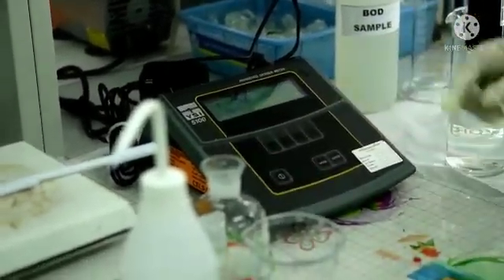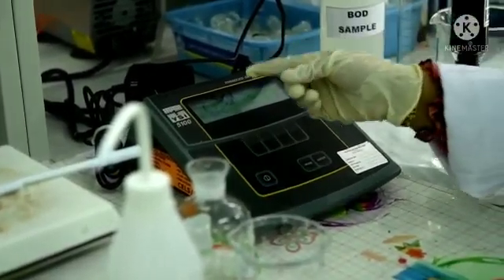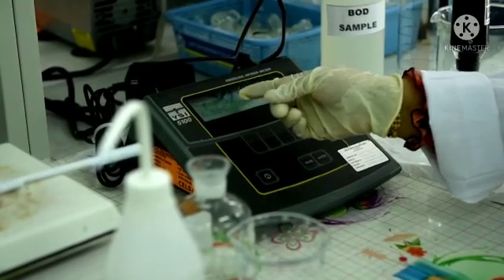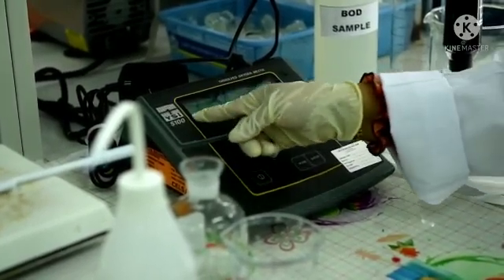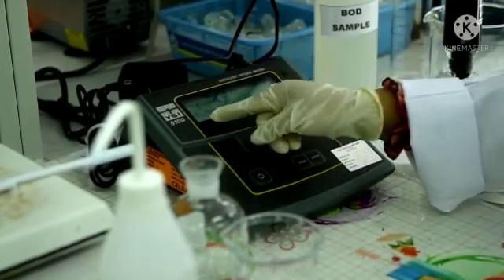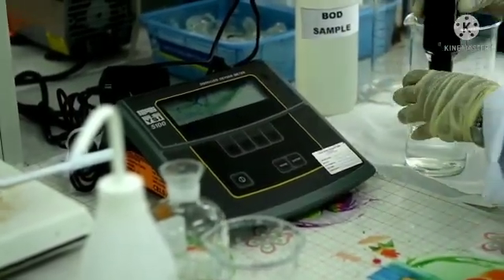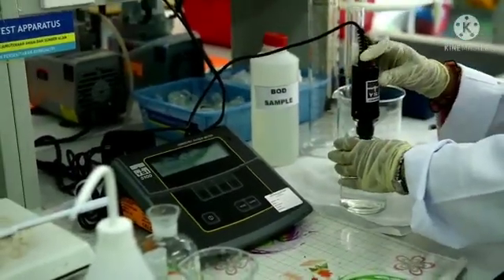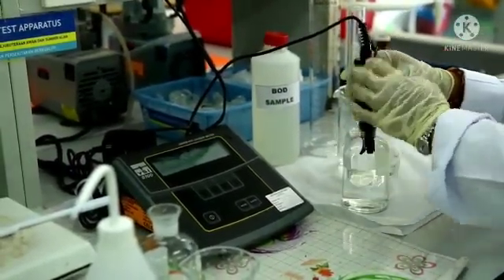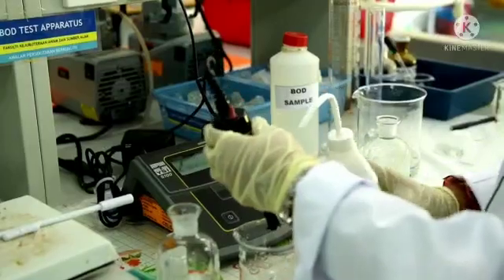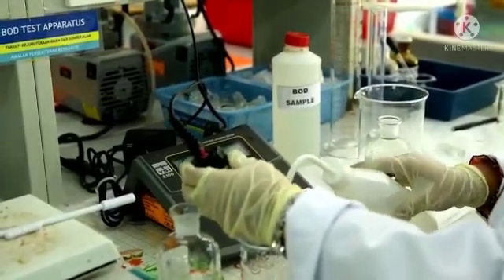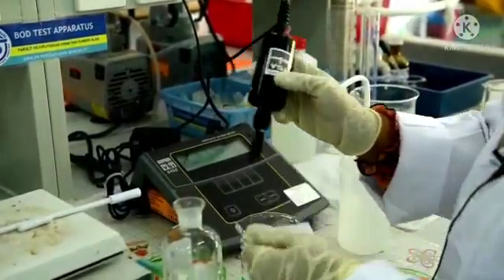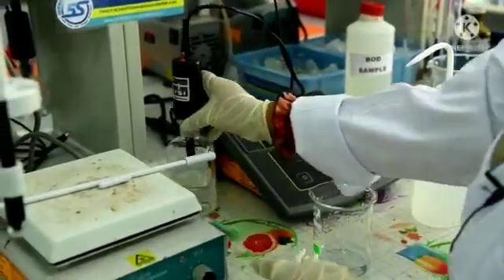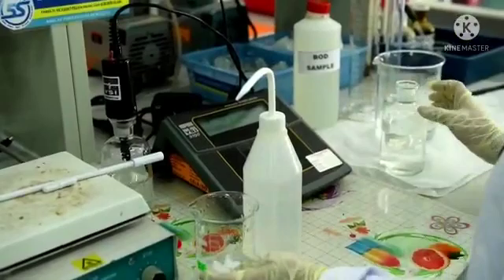You must note the first reading, for example 7.50, and you also must note the temperature, 26.54. This is the first reading, DO initial. Then you stop the stirrer, clean the probe again, and put the sample back into the bottle.